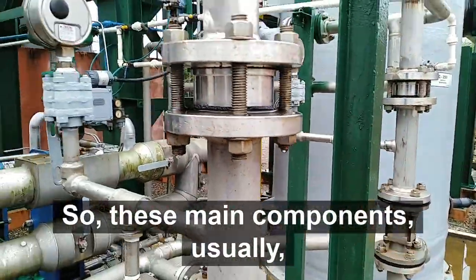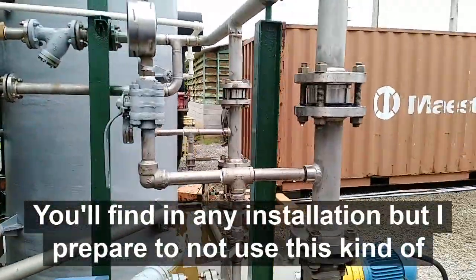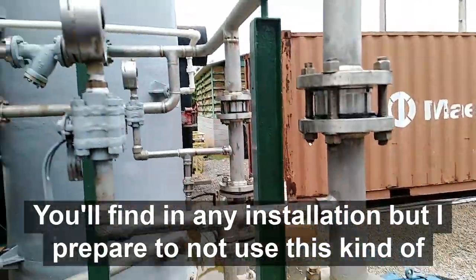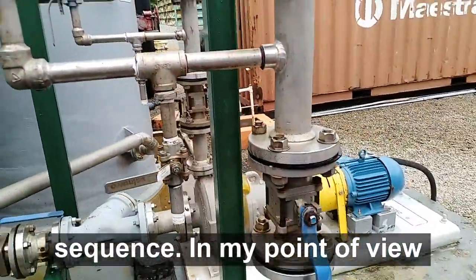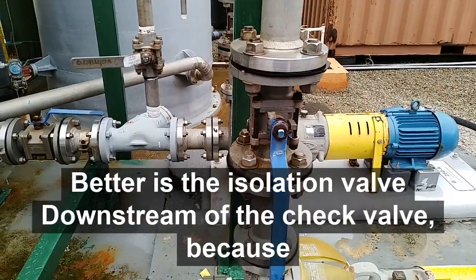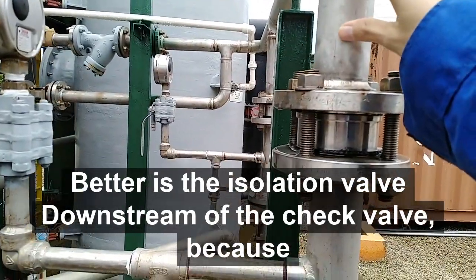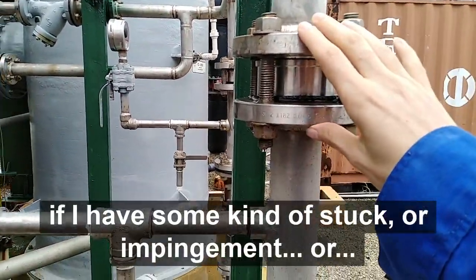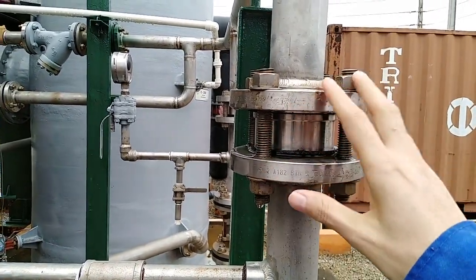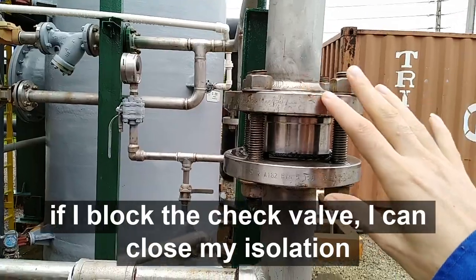and here we have a check valve. So these are the main components you usually find in any installation. But I prefer not to use this kind of sequence.